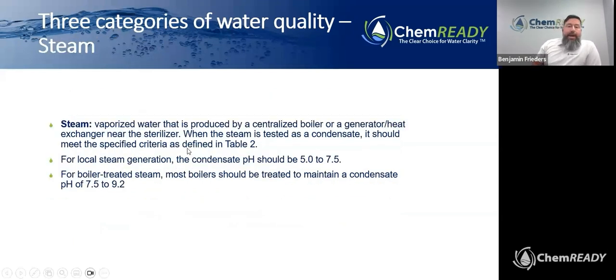And then finally, as I mentioned before, and I had my caveats about steam in terms of AAMI ST108, vaporized water that is produced by either a centralized boiler or a generator / heat exchanger near the sterilizer. So it's not the steam inside the sterilizer itself. If it generates its own steam, again, it comes from an external source. The notes here, and we'll talk about the water quality parameters shortly.